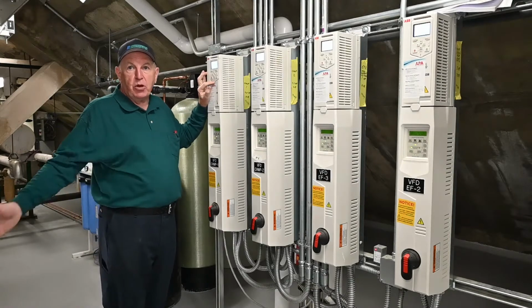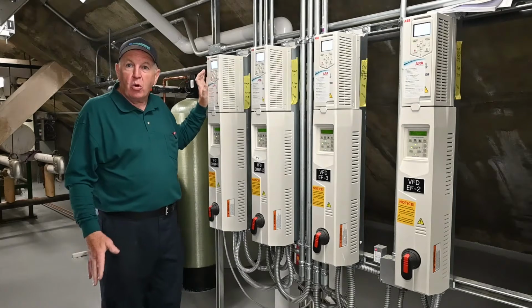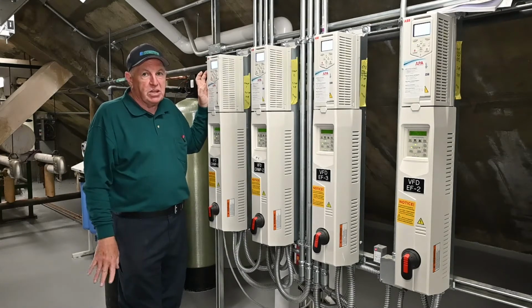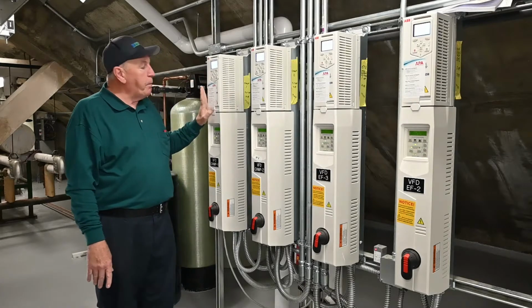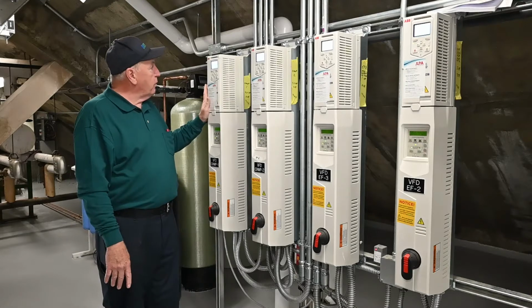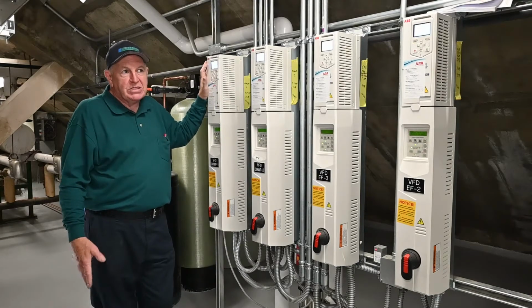If for some reason the computer program was not working, you need to run them. You can run them on hand, but you don't know what the differential pressure is. So almost always it'll be on automatic. And if one pump fails, the other one will automatically turn on. Right now we're running at 49 hertz, so the valve is probably halfway open.